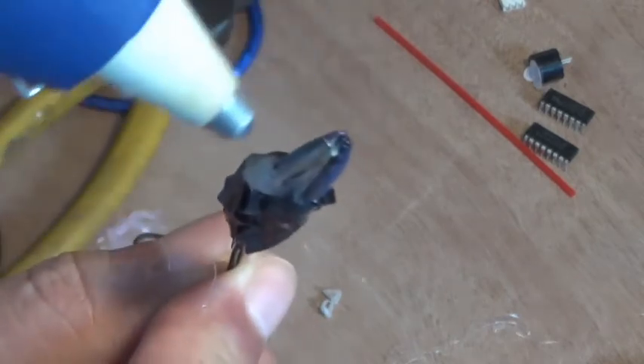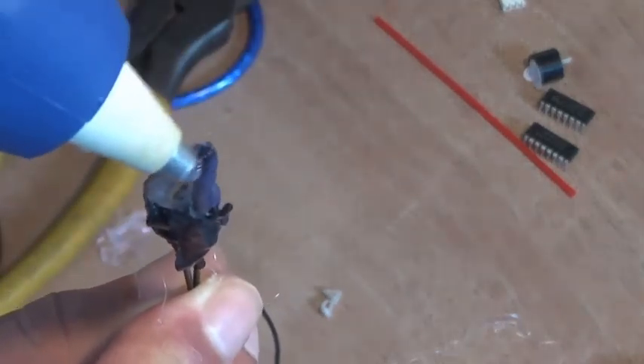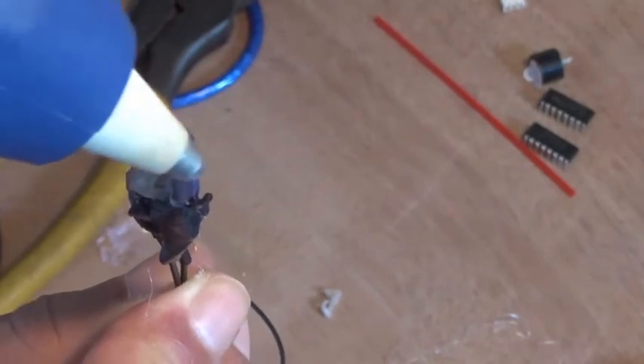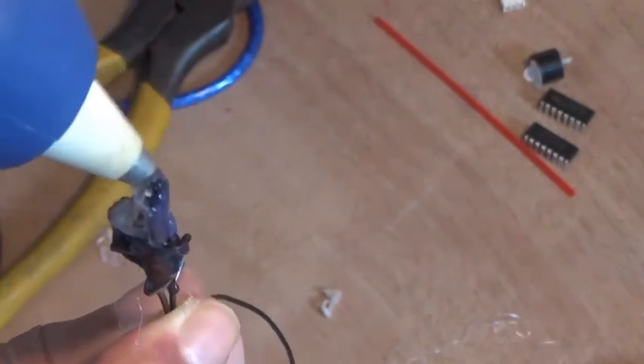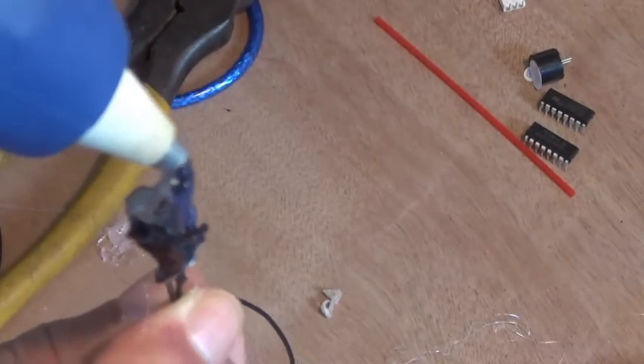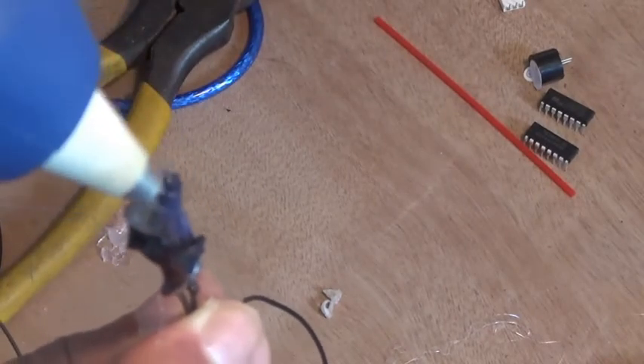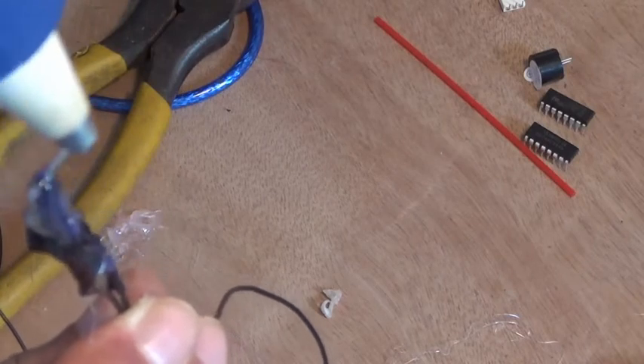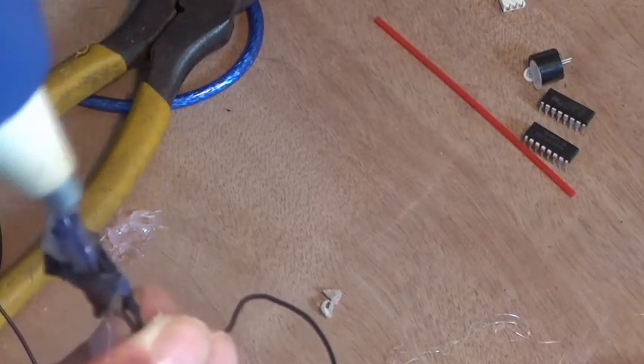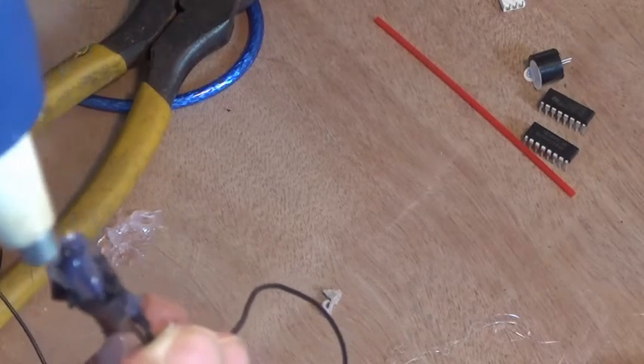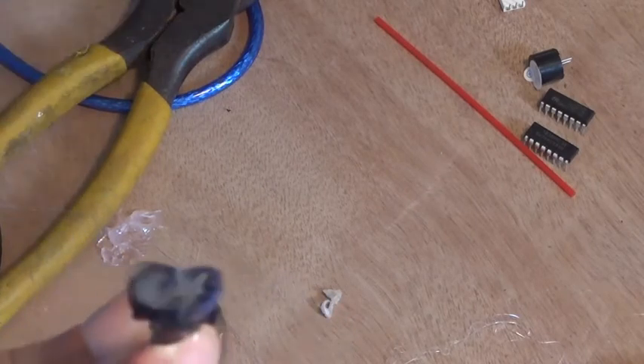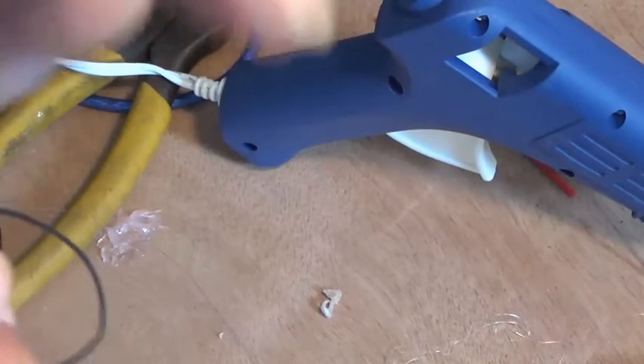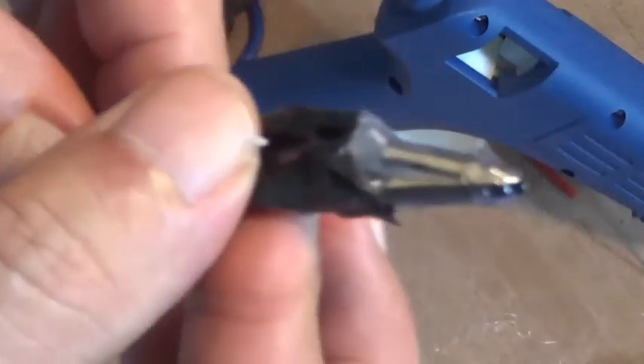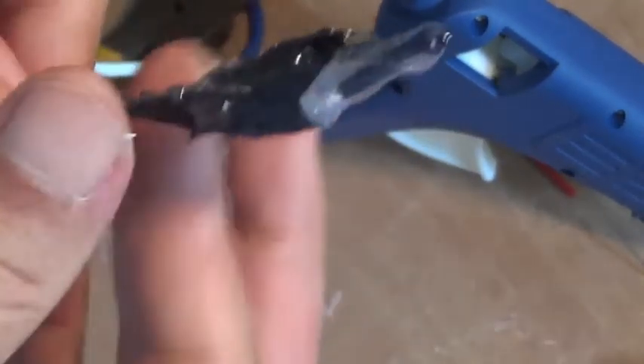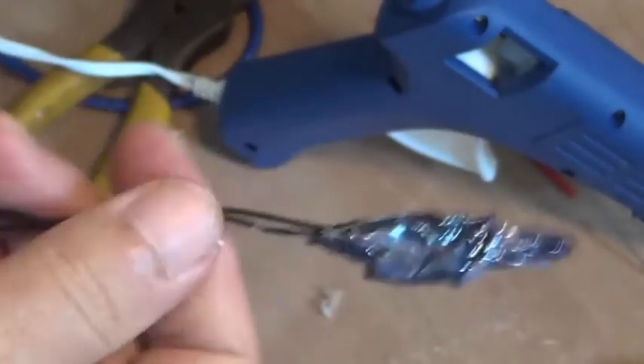Just to ensure, I'm putting a little bit more on the right at where I might get water by capillary action. I don't want that water to go through. In fact, I might want to add a little bit more right at the tip there, and then use a knife to cut any excess on top of the tip. But I just wanted to be sure that it's well covered. No water can get in. How about that? Weird, but it works. It will work. We'll test it.